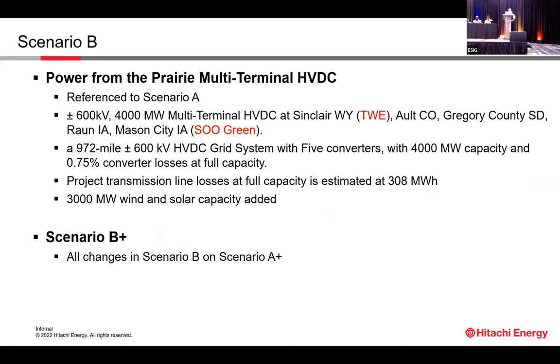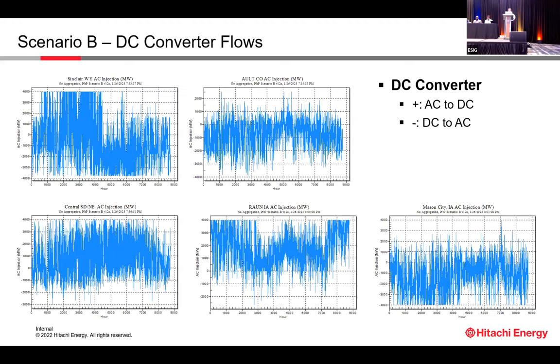And when we build scenario B, it's a multi-terminal HVDC from Wyoming to Colorado, to South Dakota, to Iowa, all the way along the line: five stations, 900 megawatt, 900 miles and a 600 kV HVDC system. Then the five converter stations operate individually. You optimize the five converters simultaneously and find where the best transfer between them is.